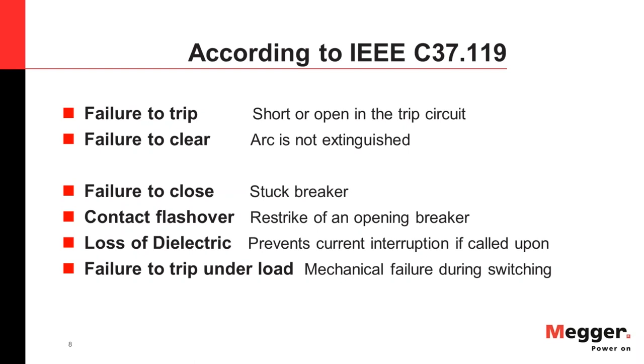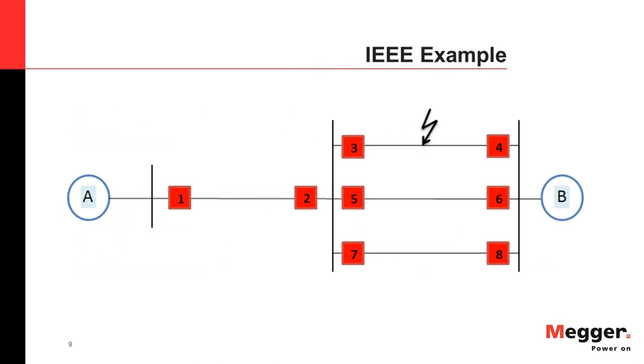Failure to Trip means a relay issues a trip and energizes the tripping coil for the breaker, but due to a short or open in the trip circuit or some mechanical problem, the breaker is unable to trip. Failure to Clear means the tripping coil is energized, the breaker is opening, and the 52A contacts get picked up, but the arc is not extinguished — that is also classified as a Breaker Failure.